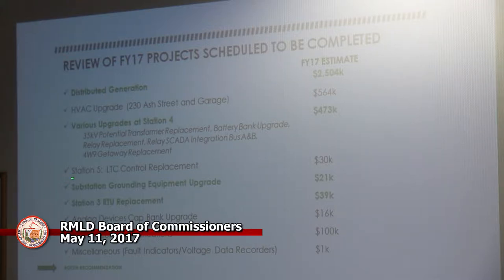At Station 5, the LTC control replacement - we had a problem at that substation with the transformer LTC, that's all fixed. The substation grounding equipment upgrade is all done. The station RTU, which is the communication device between Station 3 and the local control room or SCADA at the control room, is installed now.